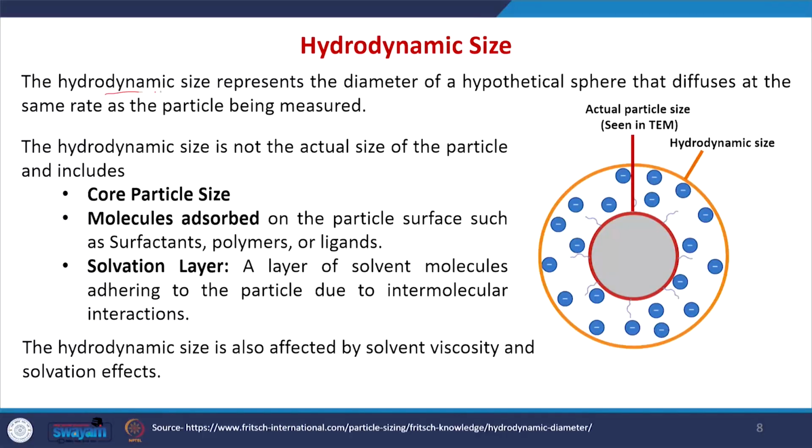The hydrodynamic size represents the diameter of a hypothetical sphere that diffuses at the same rate as the particle being measured. That is why this hydrodynamic size is not the actual size of the particle, because it includes the core particle size along with the molecules adsorbed on the particle surface. It may be surfactants or polymers or ligands, and also the solvation layer, that is the layer of solvent molecules adhering to the particle due to intermolecular interaction. The hydrodynamic size is also affected by the solvent viscosity and solvation effects.